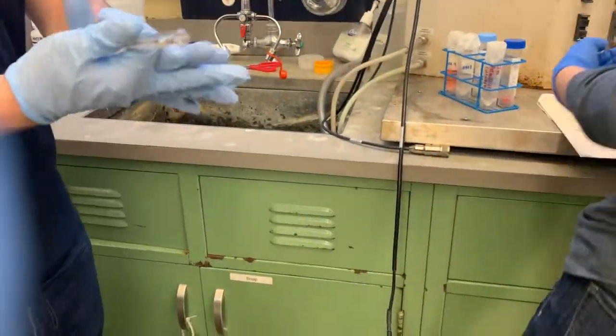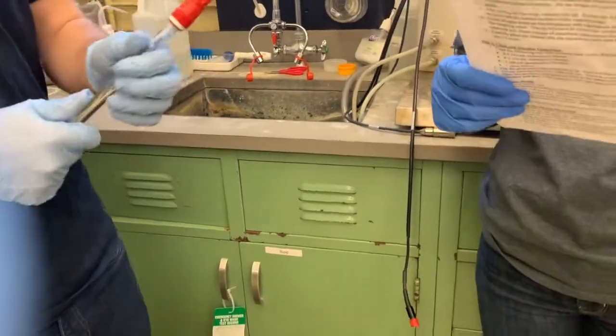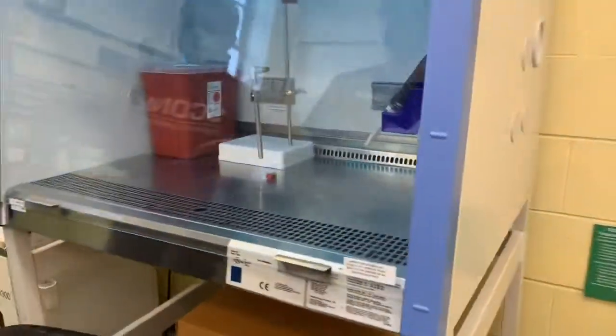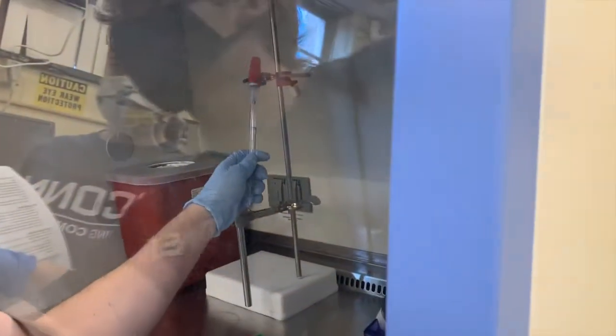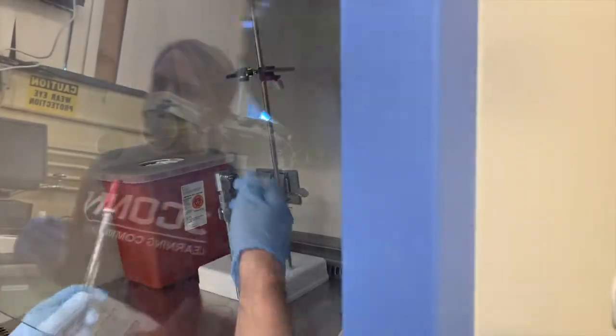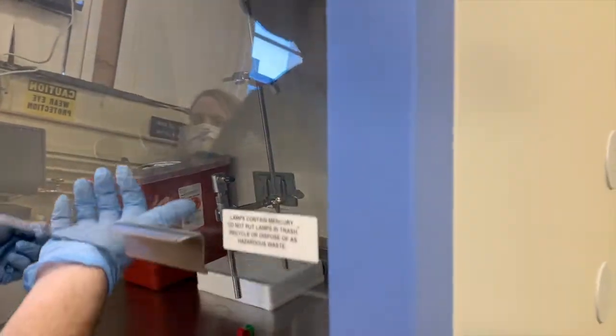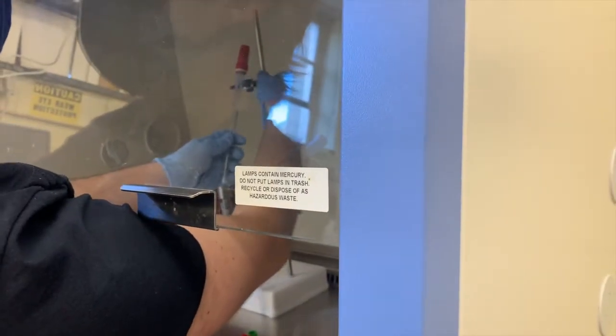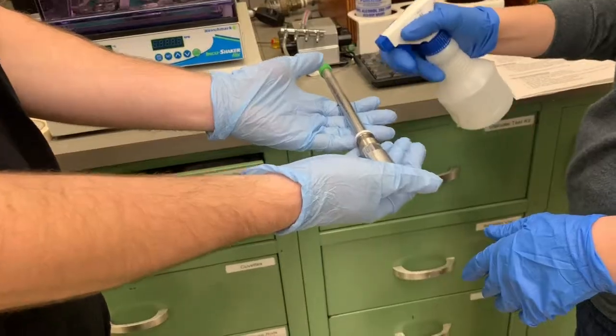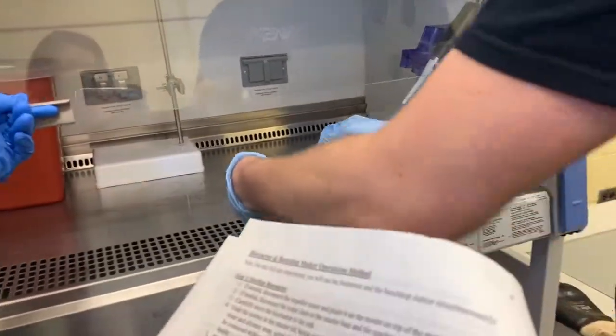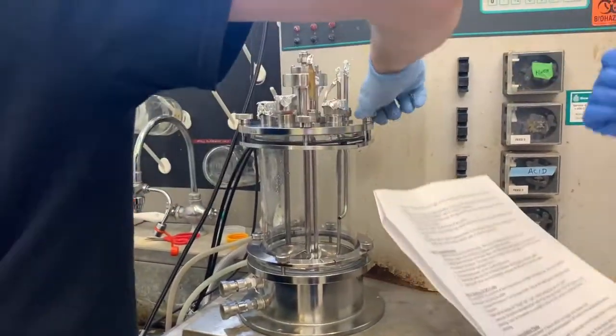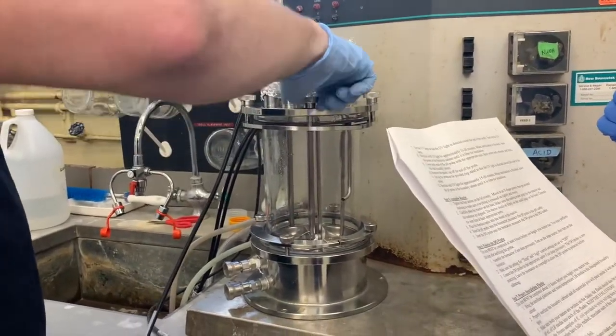The pH and dissolved oxygen probes were cleaned, sterilized under UV light, and calibrated. In addition to cleaning and calibration, the DO probe was allowed to polarize overnight before use for the experiment. The bioreactor was then assembled and double-checked to make sure everything was in order.